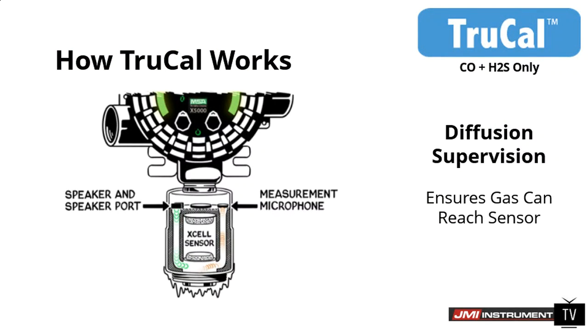So the way this works is we emit a sound from the speaker port, and that travels over the frit of the sensor, and that's picked up by the microphone. What that actually does is look for a frequency change on the sensor itself. So if it's free and clear, the sound won't change. And if the sensor is blocked, like you see here on the screen, you might see some ice buildup, sludge, dirt, mud, snow, whatever it might be, could be blocking that sensor. That frequency of sound is going to change, and we're going to be able to pick that up.